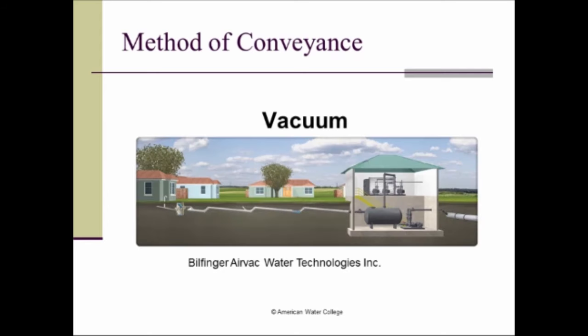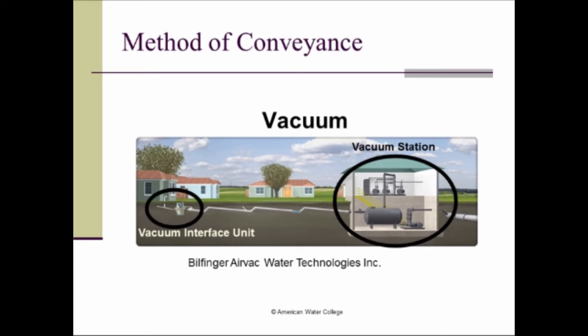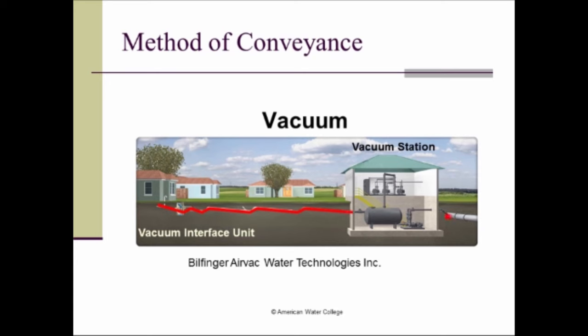The last system is the vacuum system. In the vacuum system, a vacuum station provides the low pressure that serves as the motive force to draw the wastewater in one direction. Near the residence, we have the vacuum interface unit, which interfaces between the gravity portion of the building sewer and the vacuum system on the municipal side. The vacuum station provides the force that draws the wastewater to the wastewater treatment plant.